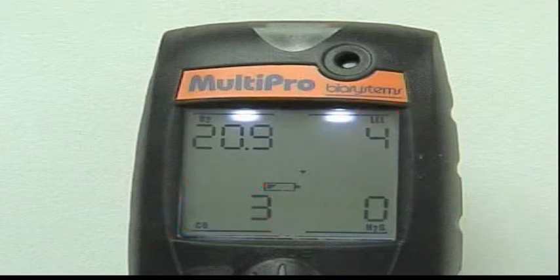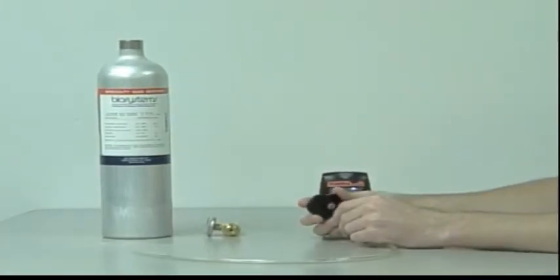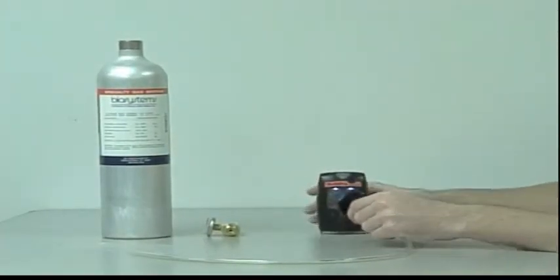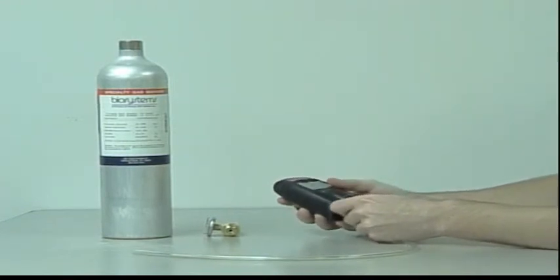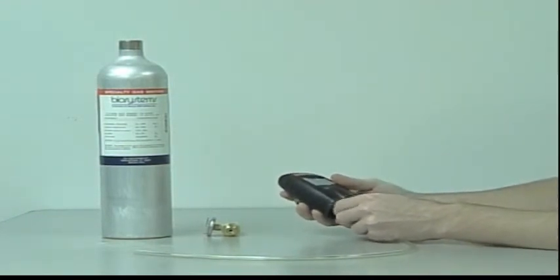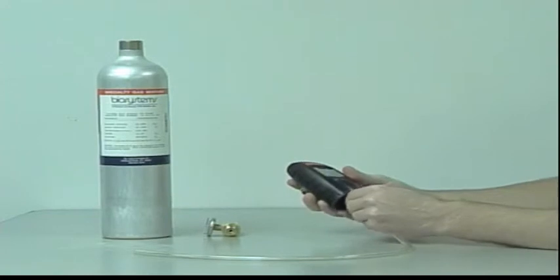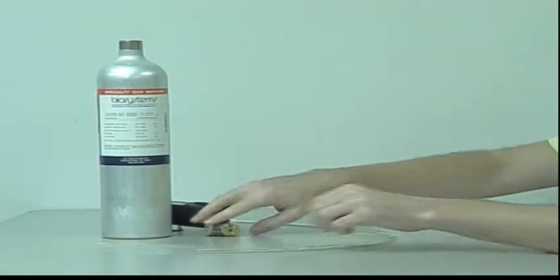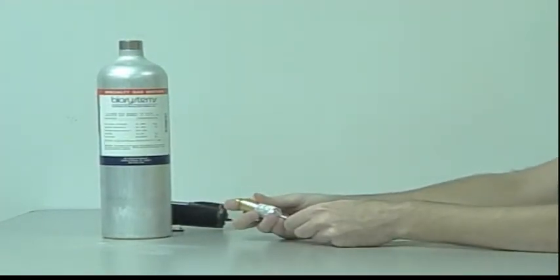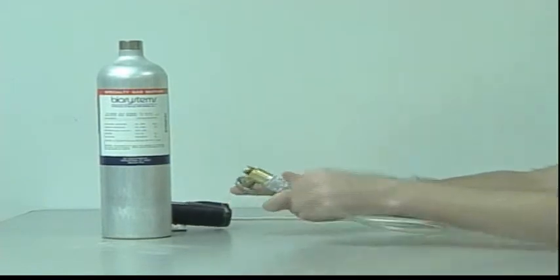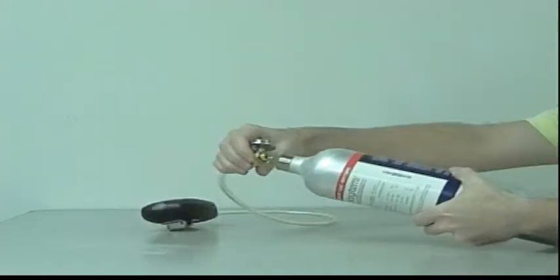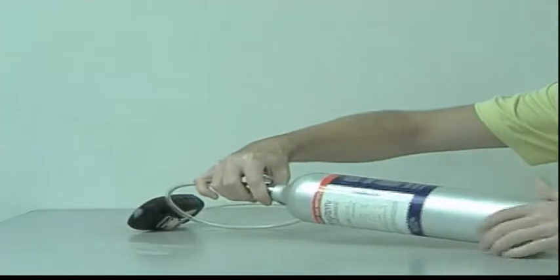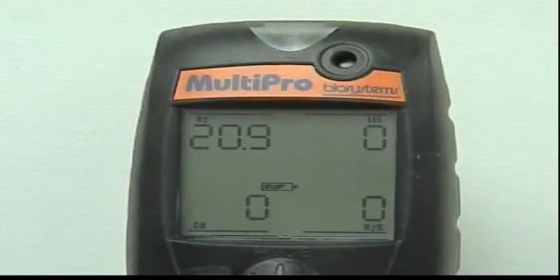Attach the calibration gas cylinder, regulator, and calibration adapter with a short section of tubing to the MultiPro. Make sure that the cylinder threads and seating surfaces are clean and dry when attaching the regulator to the gas cylinder. All-in-one calibration mixtures are especially convenient when doing a bump test. Flow gas to the sensors and allow the readings to stabilize. 45 seconds to 1 minute is usually sufficient. The alarms should activate.